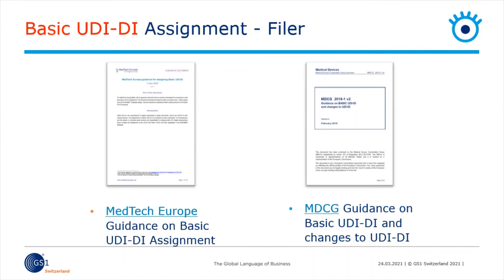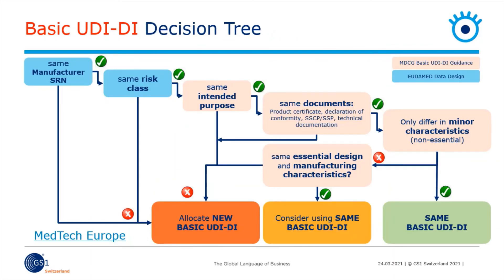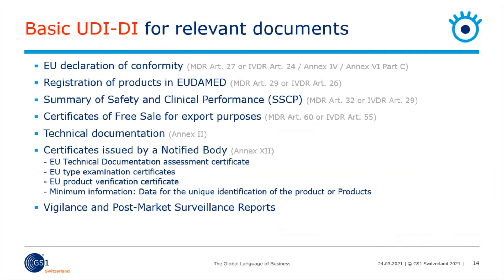There are two helpful guidelines: one from MedTechEurope and the guidance of the MDC Group. Both can be downloaded with the provided link. In the guidance of MedTechEurope, you will find a decision tree. This decision tree should help you with grouping your devices. The grouping is one of the most important steps when implementing UDI.